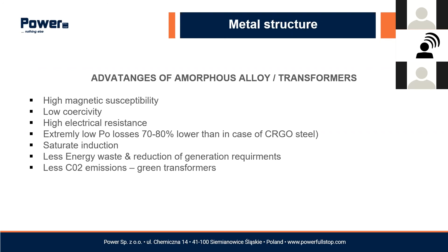Of course, high magnetic susceptibility, low coercivity, high electrical resistance, saturated induction, but there are also some negative points. Lower efficiency at full load. That's why amorphous transformers sold here in Europe are exclusively distribution transformers. All distribution transformers almost in all countries run up to 70–80% load, not higher. For that reason, amorphous transformers are in 99% of cases used for the distribution market.